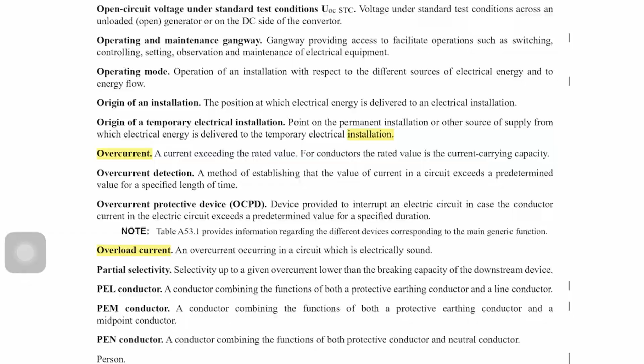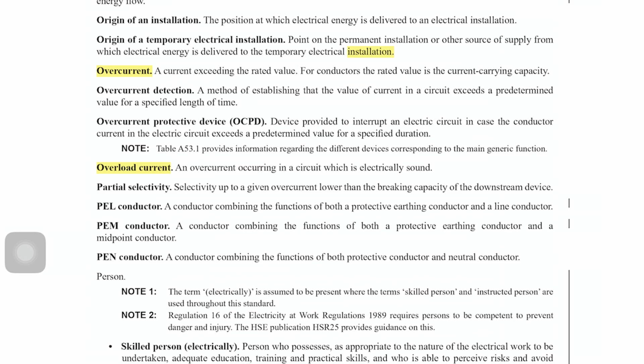So when it comes down to an overload, there's actually nothing wrong with the circuit. It is an electrically sound circuit. What you've done is abused it. For example, if you go home today and plug in the washing machine, the kettle, the tumble dryer, the microwave oven, the toaster, whatever it is, and just keep putting it on, you've overloaded the circuit. There was nothing wrong with the circuit, you've just abused the circuit. It's the same with a motor. So when you're working on your production lines, if you've got conveyor belts and you keep putting boxes on it and more loads, it's going to put extra stress on the motor. So again, you've overloaded that particular type of circuit, or something gets jammed maybe. There was nothing wrong with the circuit, it's an overload.